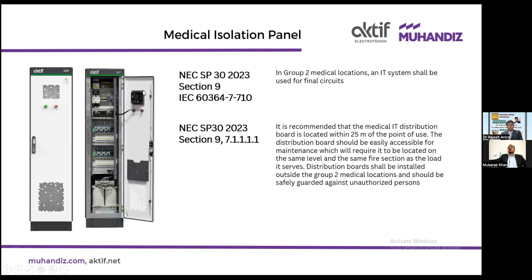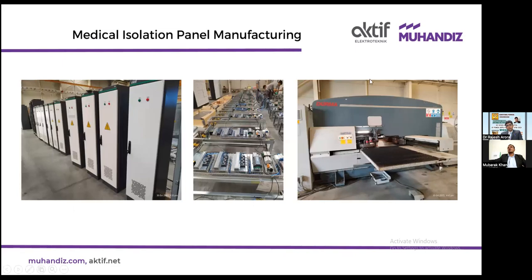Okay. So now the isolation panel, this is how it looks. It is recommended as per NEC SP30 2023, section 9, and IEC 60364-7-710, for all group 2 locations. So here is the detail. It says that it should not be further than 25 meters, and it should be within the fire zone. And one medical isolation panel should be there for each operation theater. Such provisions and requirements are mentioned in the NEC standard. Okay, these are some photographs of isolation panel manufacturing from our factory.